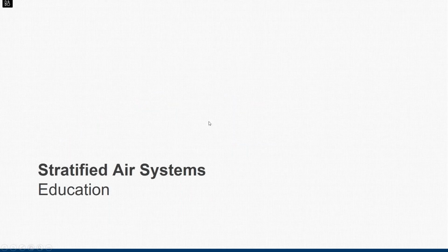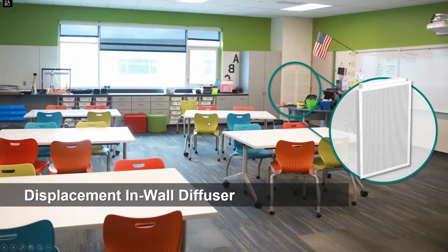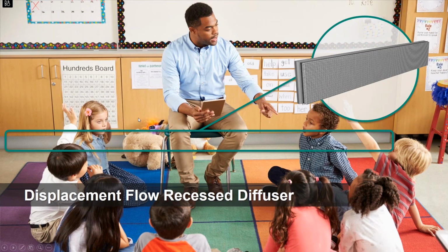All right, so getting into education, just real quickly I want to talk about the different methods of displacement, shifting from underfloor air to an in-wall displacement approach. Here's the most common way that we see it installed, where you've got this drywall channel or chase. We've got a round duct coming down to the top of a plenum, and then you've got the displacement diffuser face installed into that plenum. So basically, there's a lot of ways in which you can supply displacement into a classroom. If you've got a school district that's used to a certain set number of furniture in the space, you can actually integrate it into the kicker and pressurize that. That way you're not giving up any more usable program area in the classroom.